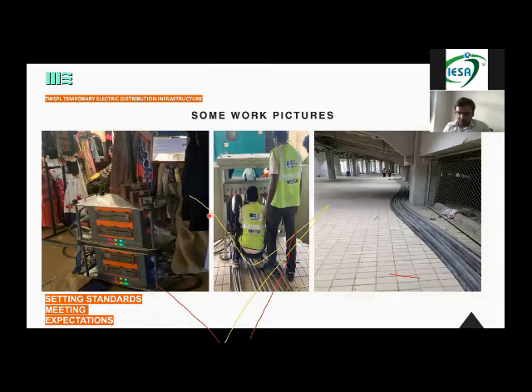It took us 1.5 years to make them understand. But now we make sure that they are always wearing their safety shoes and safety jackets when they are coming on sites. So this is a picture of the Namaste Trump event we did in the month of February. The gensets were 300 meters away. We were using aluminum armored cables because it was an under-construction site, so we didn't want to carry copper cables. Copper is expensive and prone to theft also, so you have to be careful when you are using copper cable. So over here we were using aluminum armored cables.